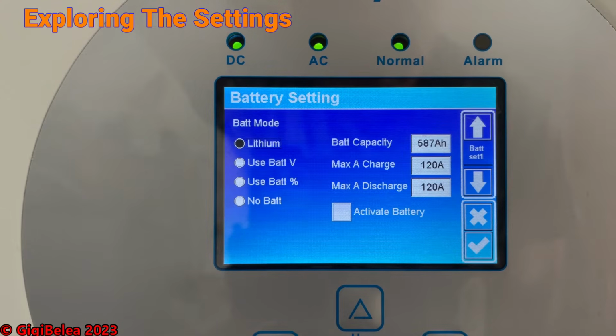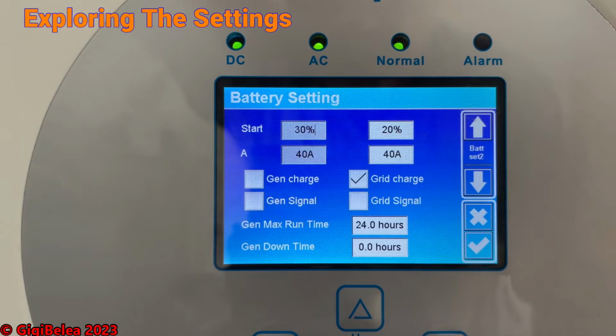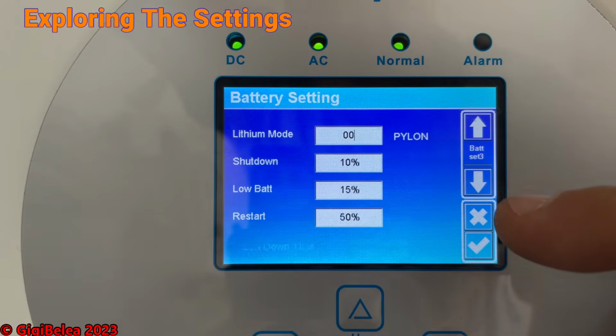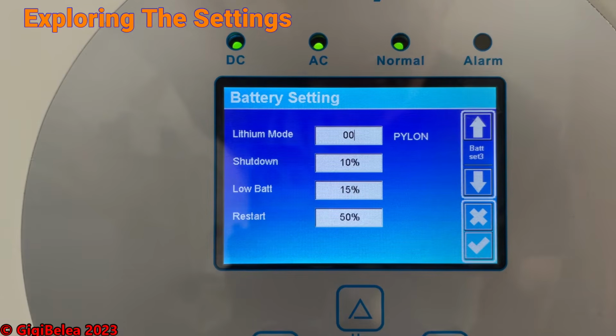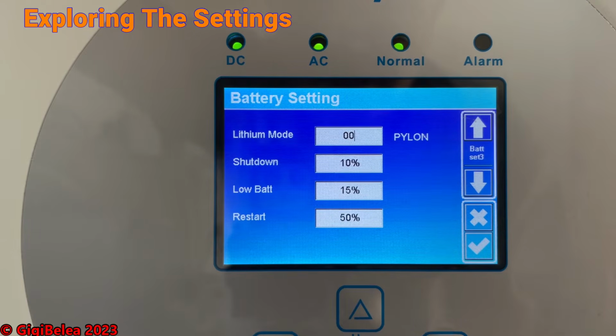Charge amperage, current and discharge, how much I want to charge and discharge the batteries with, how much it should charge from the grid, only with 40 amps I would say, and it will start charging at 20% if it goes so much. Lithium 0, that means self-adapting to lithium BMS. It will find itself the type of battery that you have. If I have the battery at 15%, it will trigger a low battery warning, and at 10% it will shut down.